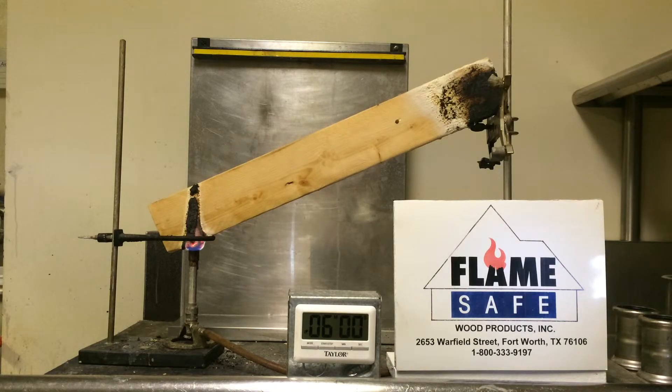Testing conducted at Intertek on OSB utilizing Flame Safe fire poly FP-100 indicated a flame spread rating of less than zero — and I say less than zero because at certain times during the test the flame actually reversed, because the carbon char increased to such an extent that the flame could not go past it, causing a back flow of the flame front. The smoke generation on OSB was 40; the standard for that particular test is 450, so you can see it's greater than ten times better as far as smoke is concerned. Smoke is always important because smoke during a fire kills more people than the fire itself.